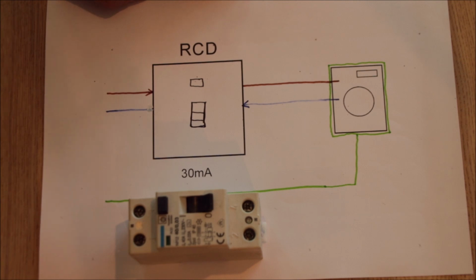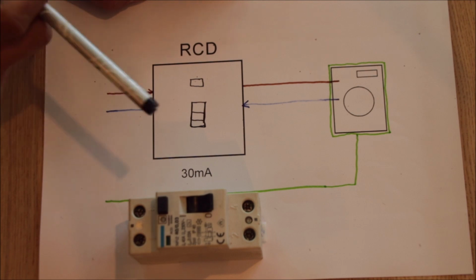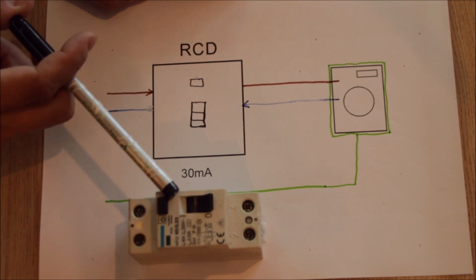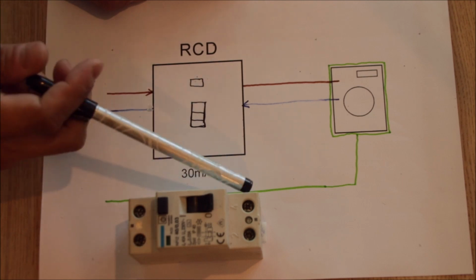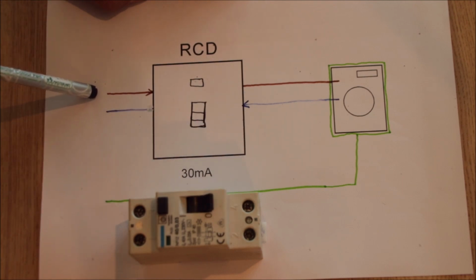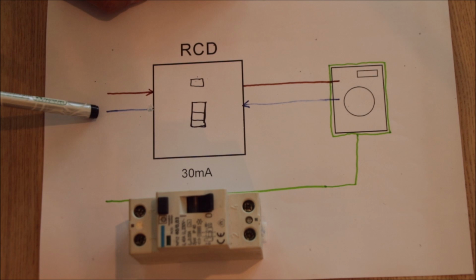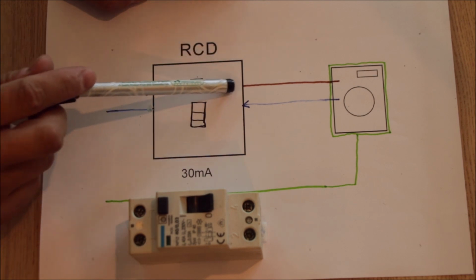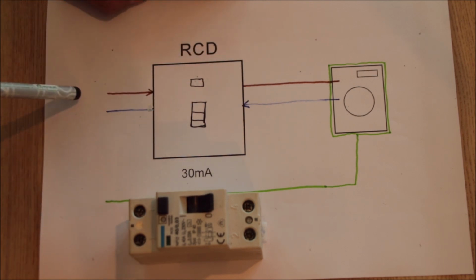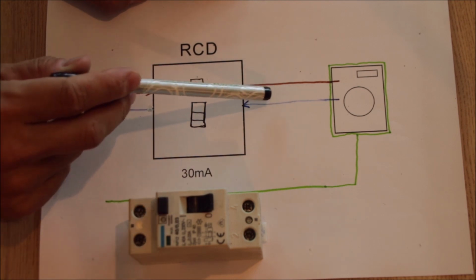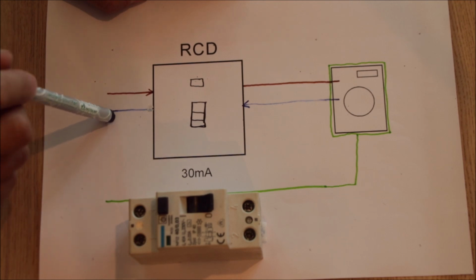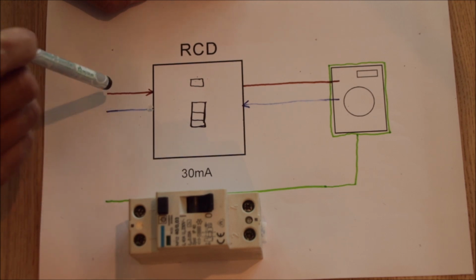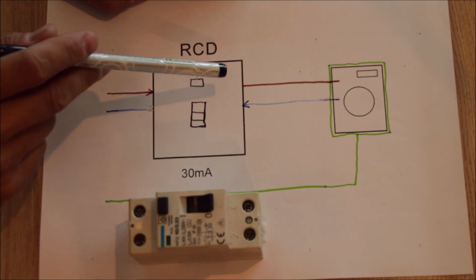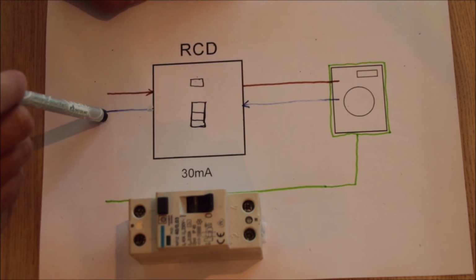RCDs are very specialized protective devices. They have a measurement circuit inside of them. They have an input and an output. You connect input wires on one side and output wires on the other side. And the device measures current in and current out. So in an electric circuit which is 100% functional, current in must equal current out.